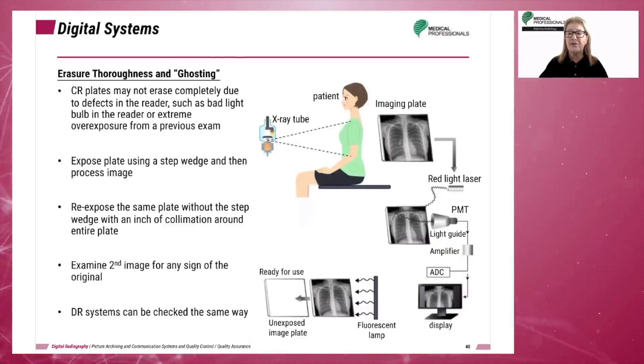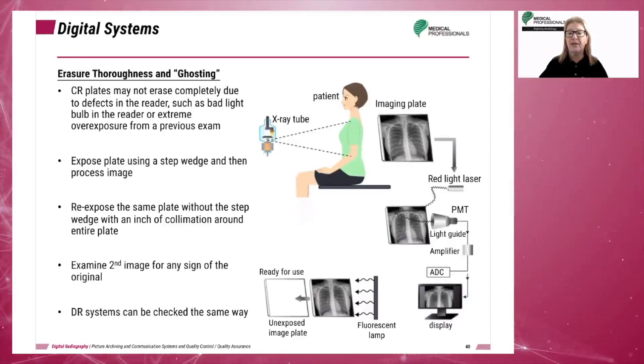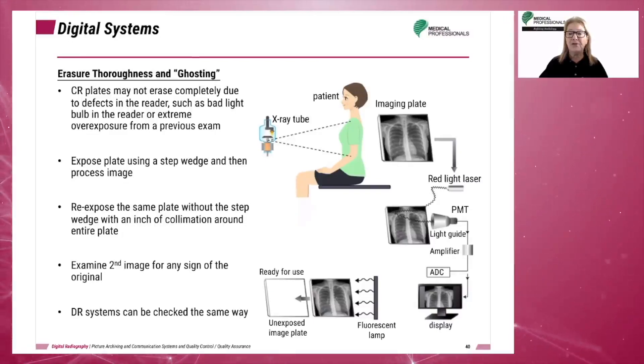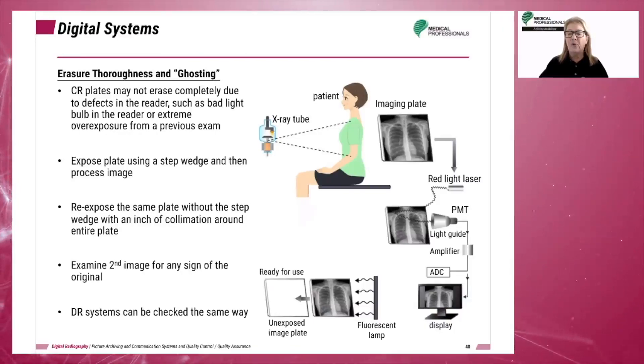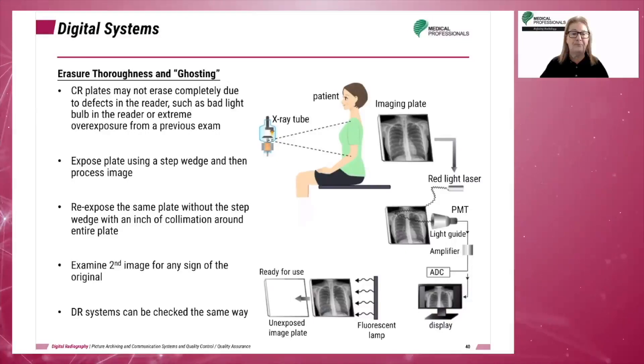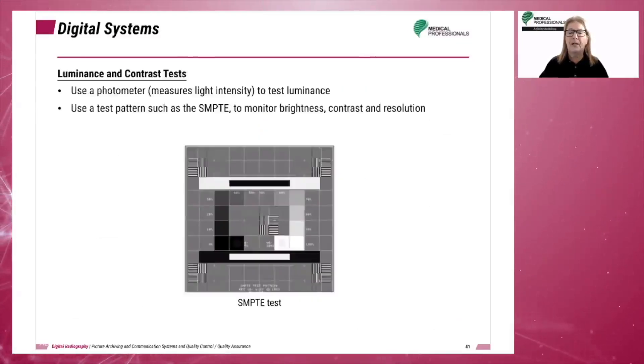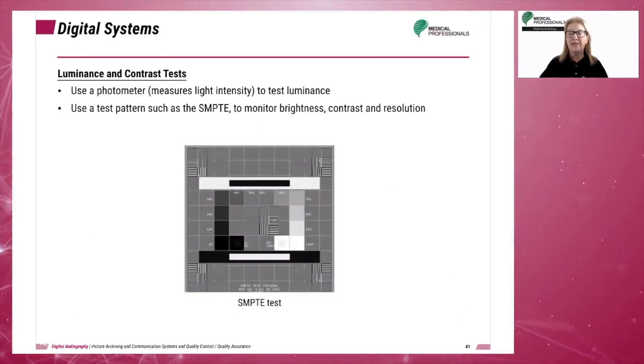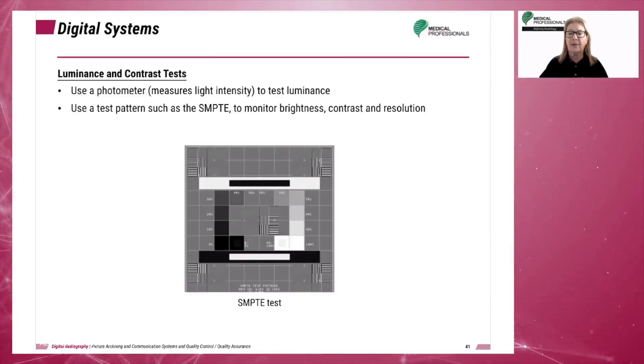Phantom images or ghosting effects may be the result of incomplete erasure of the imaging plate after extreme overexposure. In DR, image ghosting or image lag is caused when the electrical charge has been trapped in the metastable sites or F-centers of the amorphous selenium or silicon and is released slowly over time. Luminance response is the monitor's ability to accurately display different shades of brightness from a test pattern, and must be compared to adjacent shades of brightness; this function is essentially identical to a contrast test.